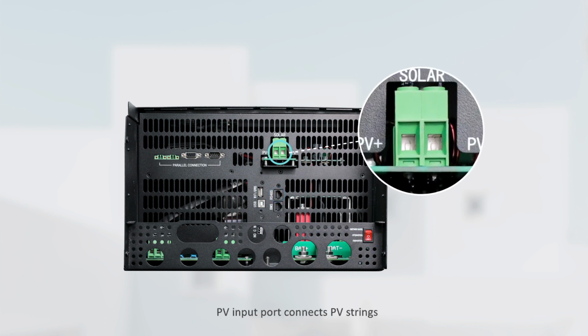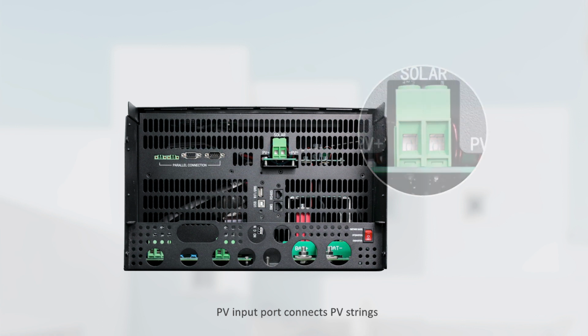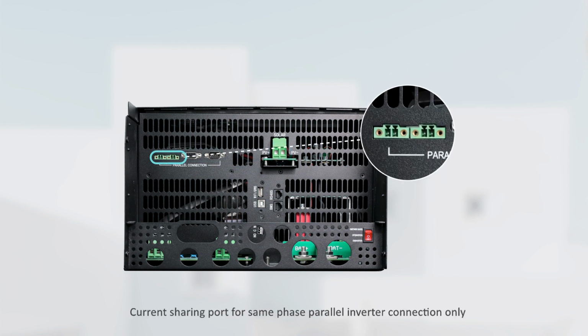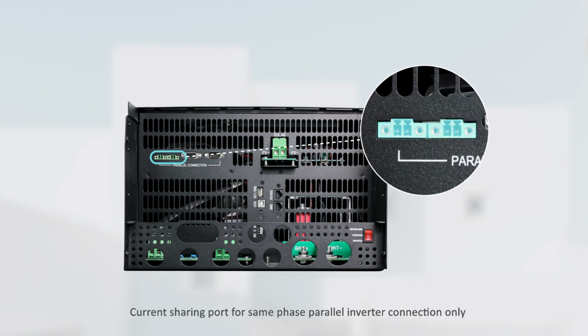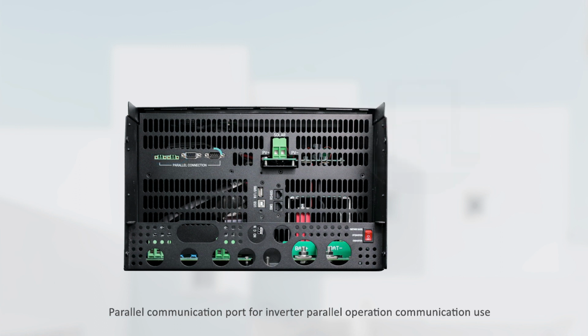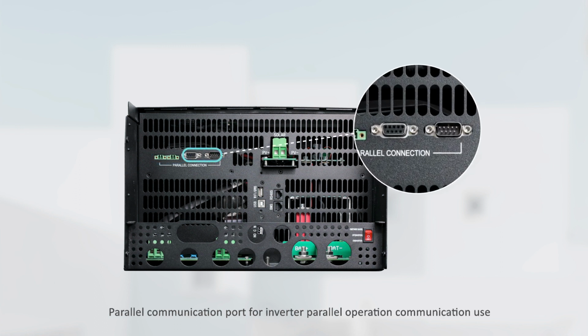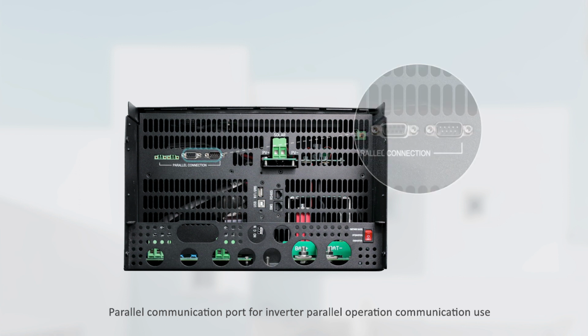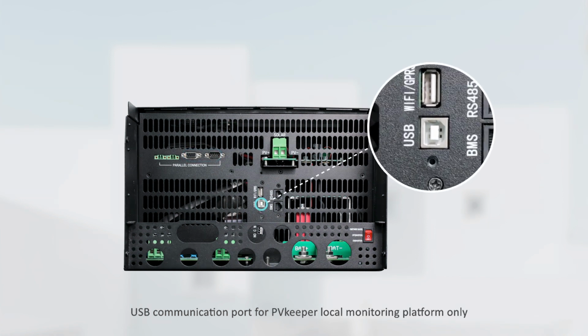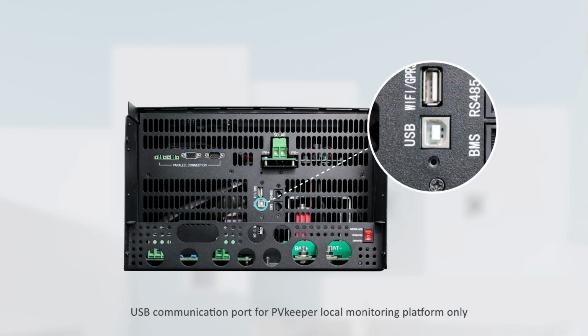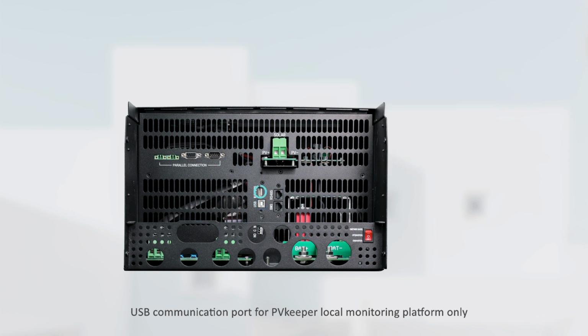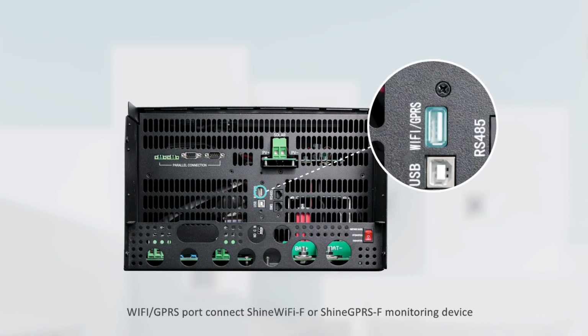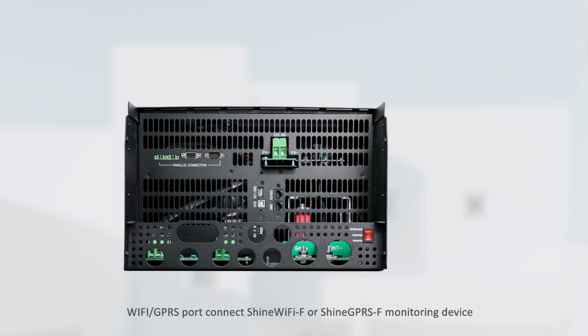The PV input port connects PV strings. The current sharing port is for same-phase parallel inverter connection only. The parallel communication port is for inverter parallel operation communication use. The USB communication port is for the PV Keeper local monitoring platform only. The Wi-Fi/GPRS port connects the ShineWiFi-F or ShineGPRS-F monitoring device.